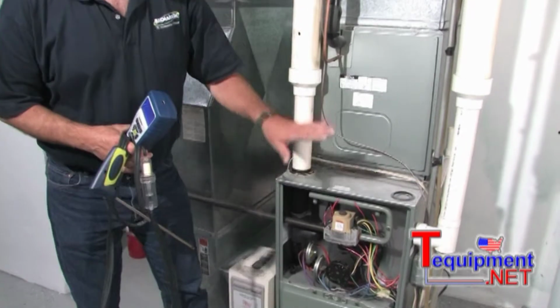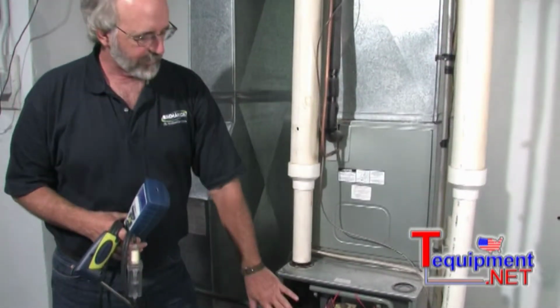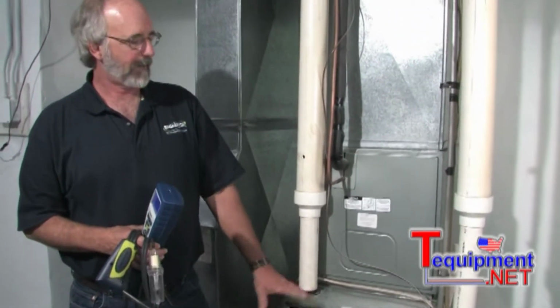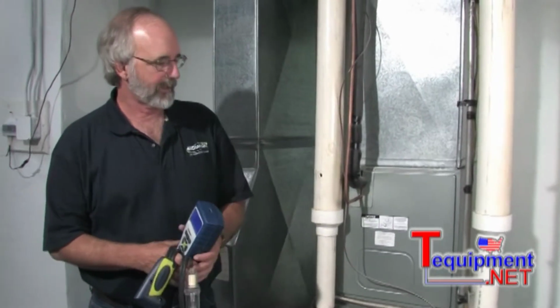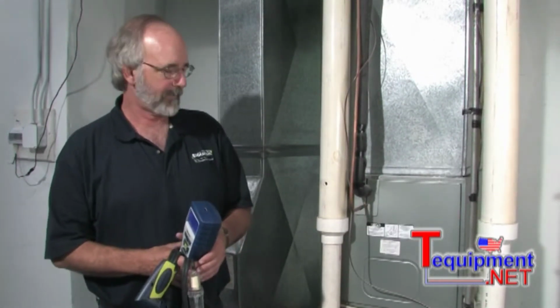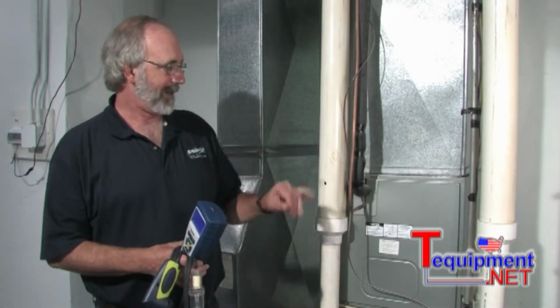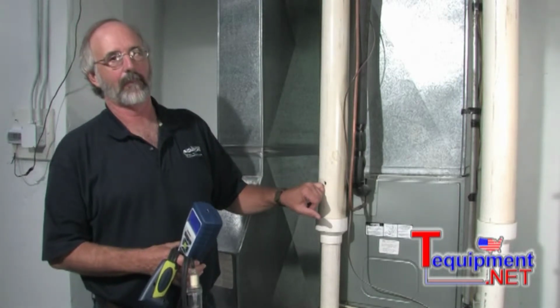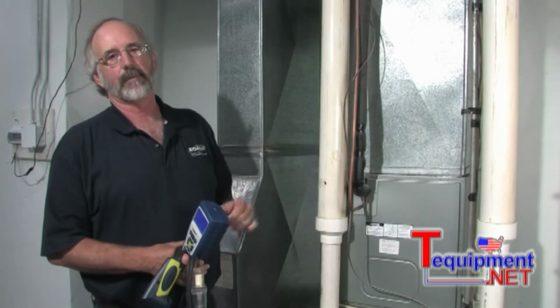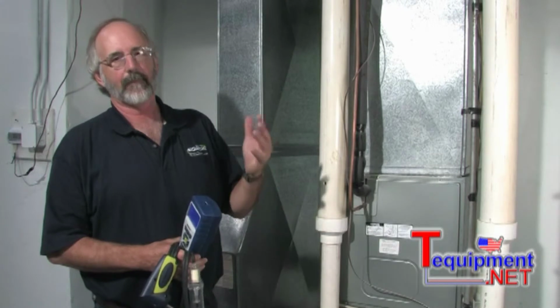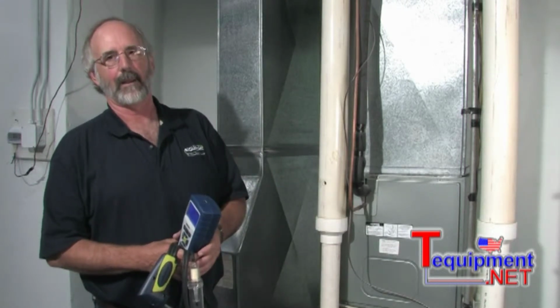We can also use it to do a static duct pressure test to make sure that that blower is providing sufficient air across the heat exchanger and across the air conditioning coil for efficient operation. And obviously we can also pull a flue gas sample out of this hole to make sure that this piece of equipment is operating safely, efficiently, and reliably.